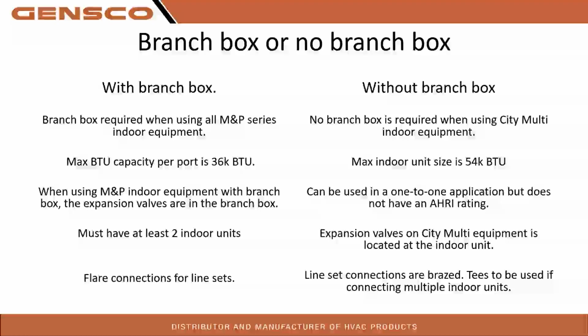Line set connections on the City Multi are all braze connections. So again, no branch box to tie all your line sets to. If you have multiple indoor units connected together, those are going to be done with pipes and tees. So, braze connections, making sure that you're actually flowing nitrogen through that line set as you're brazing. That way you don't end up with carbon buildup inside there. It's going to plug up some strainers. So we are allowed to braze on our systems. You just have to use proper brazing technique in order to keep yourself from plugging stuff up.